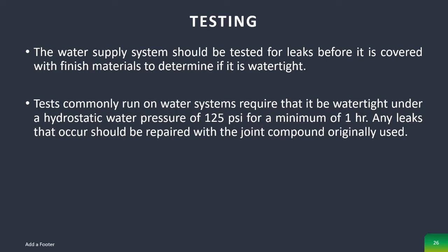Next is testing. The water supply system should be tested for leaks before it is covered with finished materials to determine if it is watertight. Tests commonly run on water system require that it be watertight under a hydrostatic water pressure of 125 psi for a minimum of 1 hour. Any leaks that occur should be repaired with the joint compound originally. So testing is a constraint para malaman agad kung may problema ba sa plumbing system.